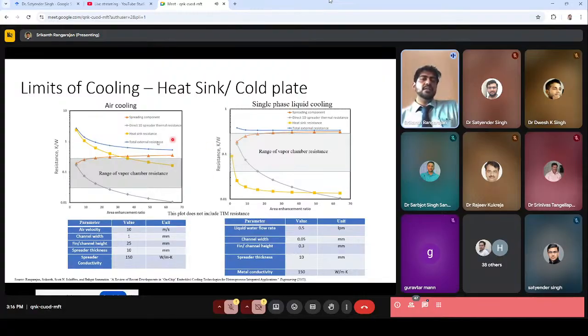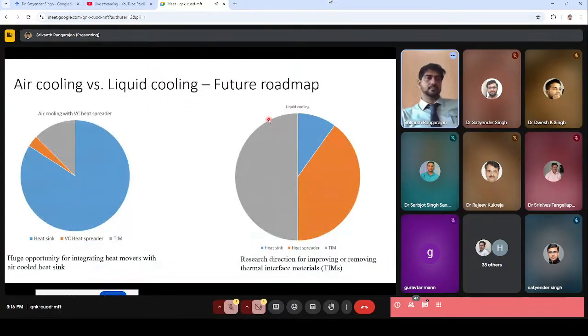From our analytical framework, we see that for air cooling and single phase liquid cooling, the cooling limits differ by an order of magnitude. As we want to achieve less thermal resistance, we have to go for single phase liquid cooling.